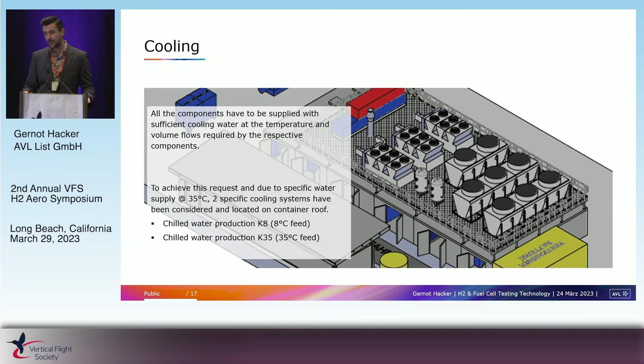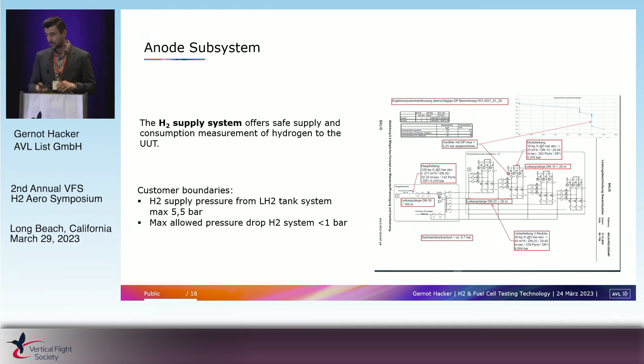The anode subsystem, or basically the hydrogen supply, also not very trivial for us. On the automotive side, we don't deal very often with liquid hydrogen supply, and specifically in this test field there are distances between the hydrogen tank test bed and the fuel cell test bed. There was also a specific requirement that we are only allowed to have a very small pressure drop between these two, because we want to have as realistic testing scenarios as possible. So we had to develop something specific for that purpose.